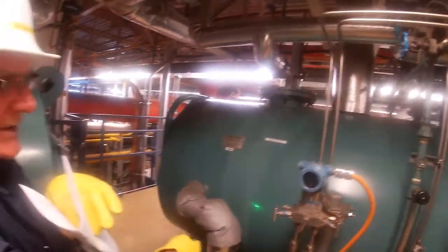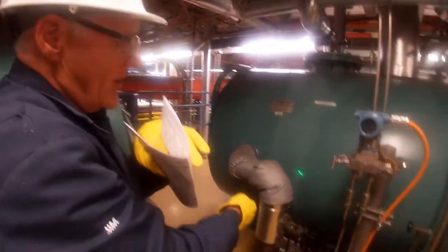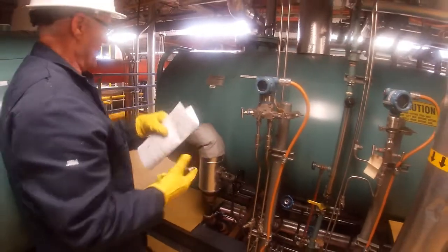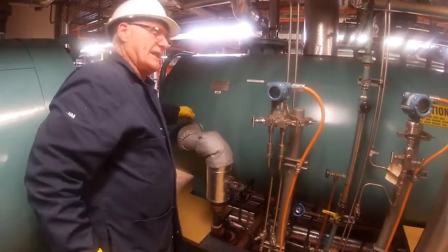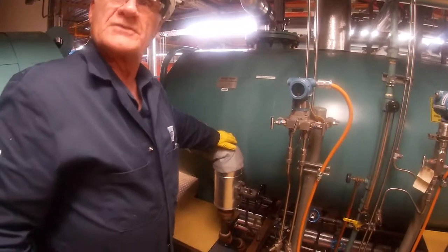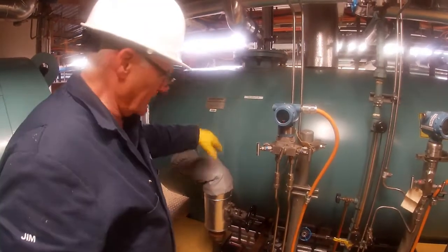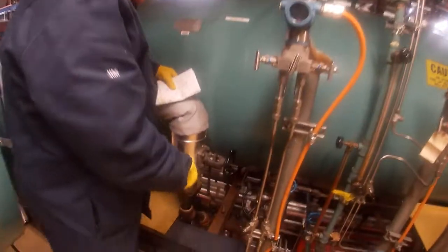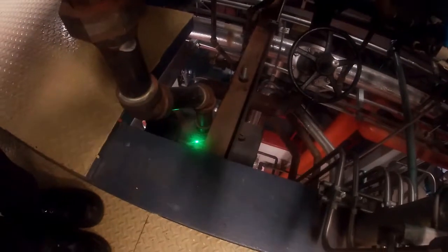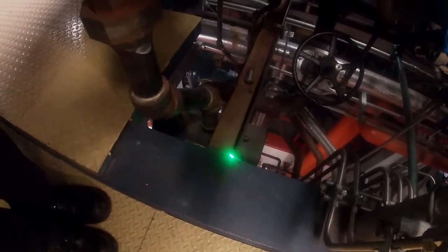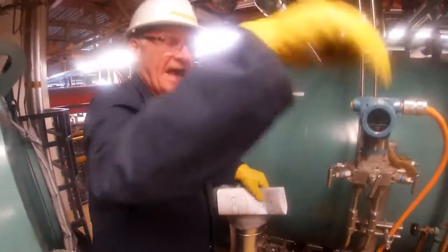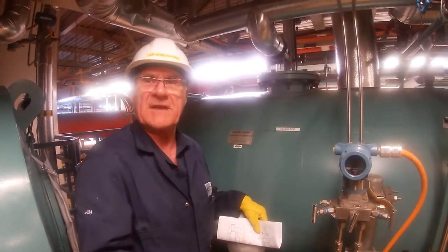In the deaerator, we control the water level down below the half level. This line right here is an overflow line, so the water level will never go any higher than that. Anything that does overflow from here goes down to a trap. I don't know how easily you can see it. The trap is right there, the great big thing, and that trap opens up for water or condensate, and that goes down to the blowdown separator in the basement.